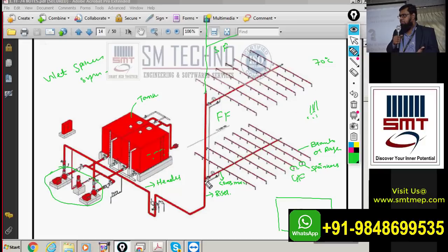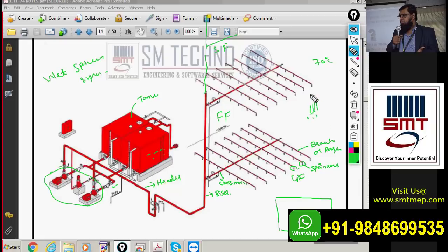When water flows through the sprinkler there is a pressure difference in the line. Because this system uses a pressure switch and pneumatic system, whenever there is a pressure difference, the pneumatic system senses it, the pressure switch operates, opens the valves, and switches on the pump. Water is then drawn from the tank and supplied to the affected area. Remember, only the affected area sprinkler opens, not all sprinklers.